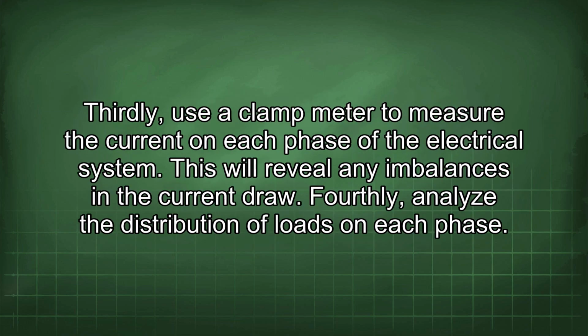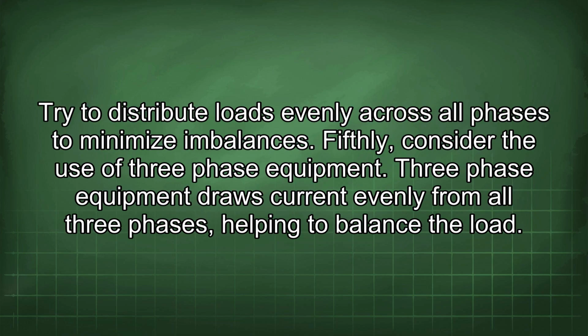Thirdly, use a clamp meter to measure the current on each phase of the electrical system. This will reveal any imbalances in the current draw. Fourthly, analyze the distribution of loads on each phase. Try to distribute loads evenly across all phases to minimize imbalances. Fifthly, consider the use of three-phase equipment. Three-phase equipment draws current evenly from all three phases, helping to balance the load.